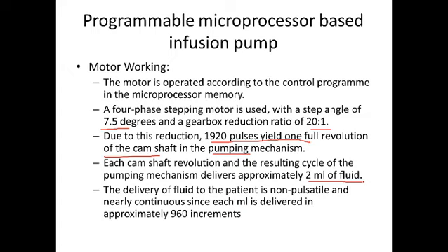You can see that you can have a very accurate pulse rate and volume control with this much resolution. It has a very good resolution. The delivery of the fluid to the patient is non-pulsatile and nearly continuous, since each ml is delivered in approximately 960 increments, isn't it?